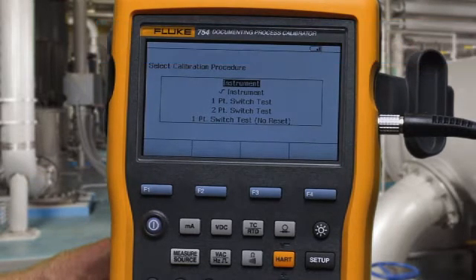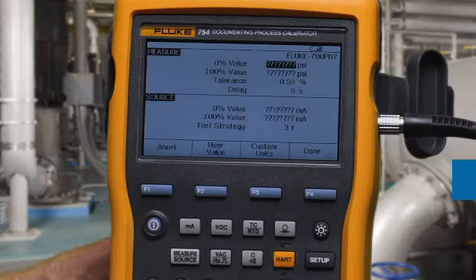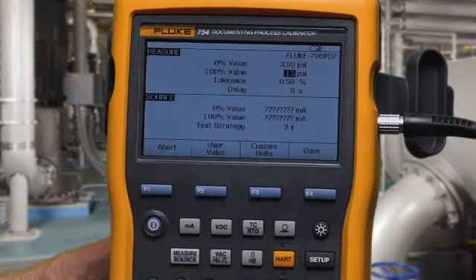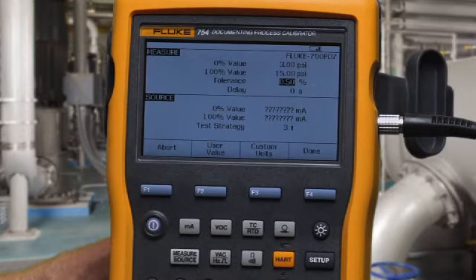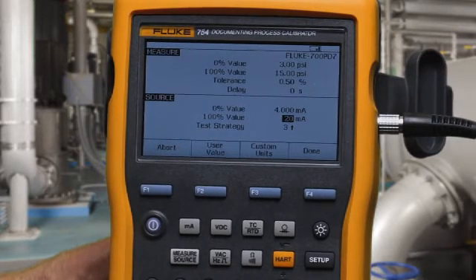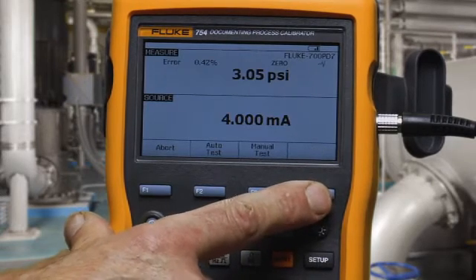We're going to measure 3 to 15 psi to 0.5% while sourcing 4 to 20 milliamps. We select Auto Test, and the calibration test will automatically perform.